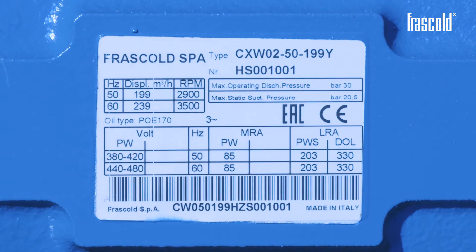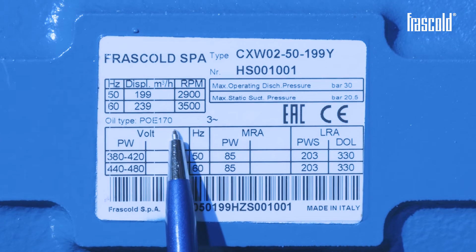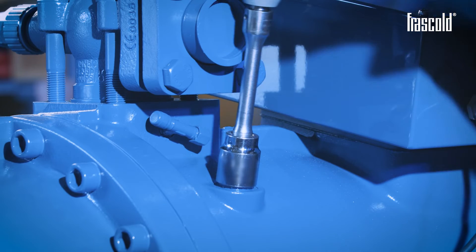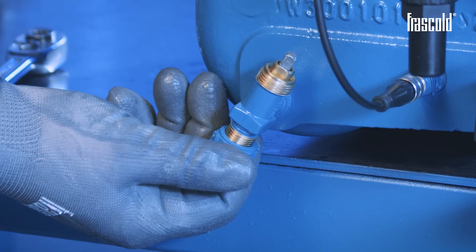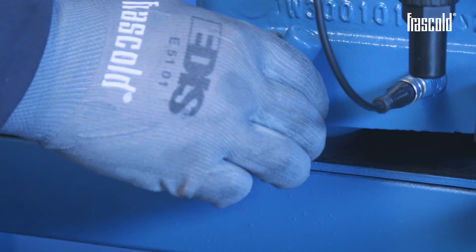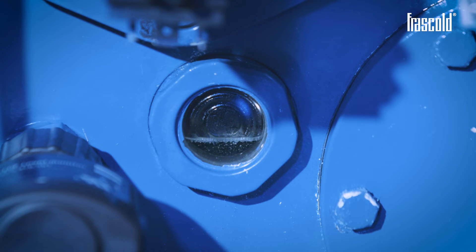At this point, the compressor can be filled with oil. Before filling the compressor, always check the type of oil indicated on the compressor label. Using a screw gun or a ratchet with a 24mm socket, open the oil filling point by removing the cap. Check that the drain valve is closed properly. Take the fresh oil and, using a special funnel, pour the oil into the filling hole. The optimal oil level should be between half and three quarters of the sight glass.